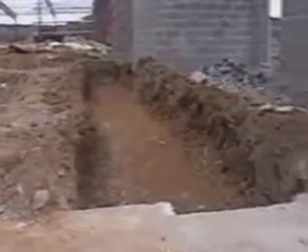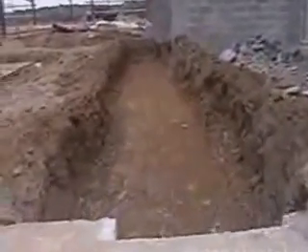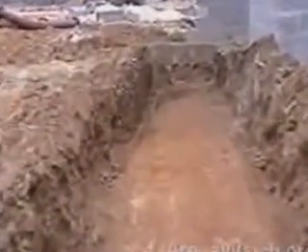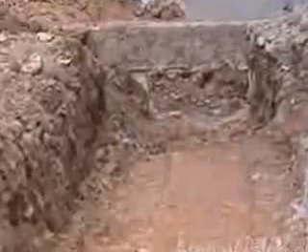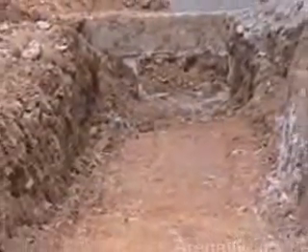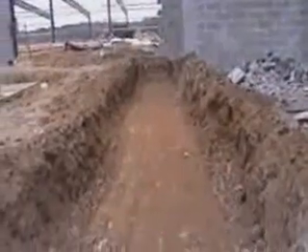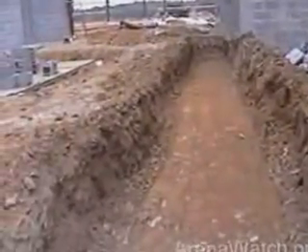Again, we're looking into the mechanical room area, of which where the chiller will be located at, and the Zamboni, which is the snow melting pit that we saw earlier. In this particular application, we have our transmission line going the whole way across the room, and the reason for that is we're going to have an additional set of stub outs on the far side of the room for hooking up manufactured chillers and running them under a load of the existing ice rink, void of the chiller that's going to be the permanent chiller for the ice rink operation.